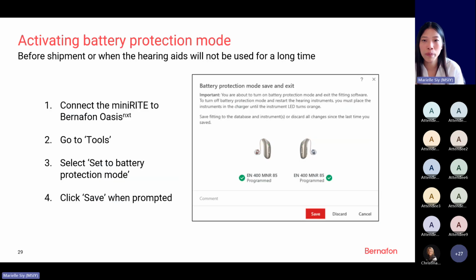You can activate this mode for the miniRITE with OasisNXT. So the hearing aids should also be put into this mode before you ship it for repair. So that's another scenario where you should activate this mode. So you should follow the steps to enable and activate this mode. First, connect the hearing aids to OasisNXT using NoaLink Wireless, and then go to Tools, click Set to Battery Protection Mode, and after you click Save, there will be a pop-up window that you see in this slide, and the hearing aids will then automatically disconnect from the software, and you can leave it as is. The battery protection mode is on.